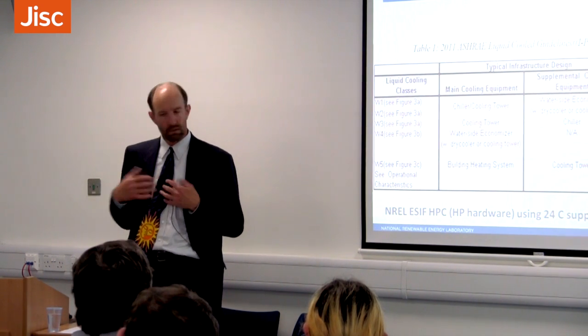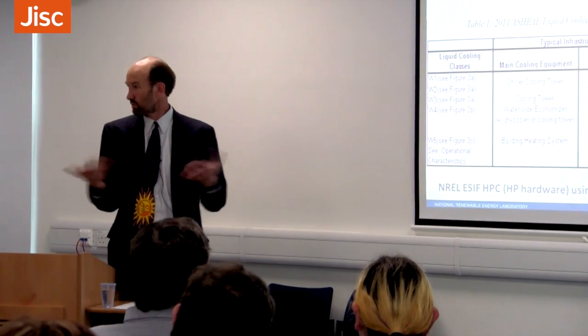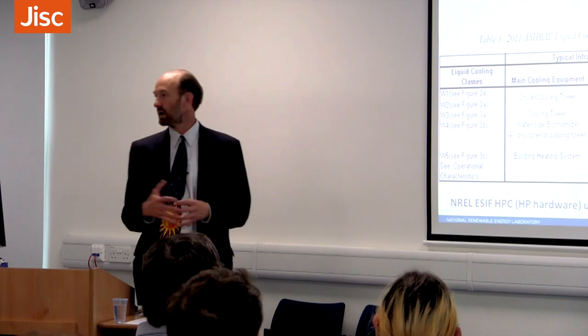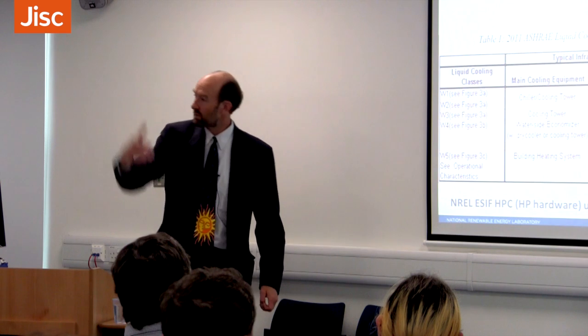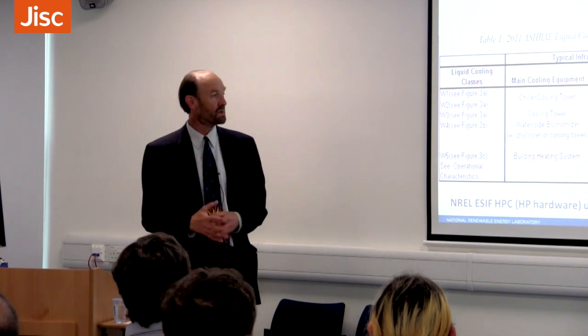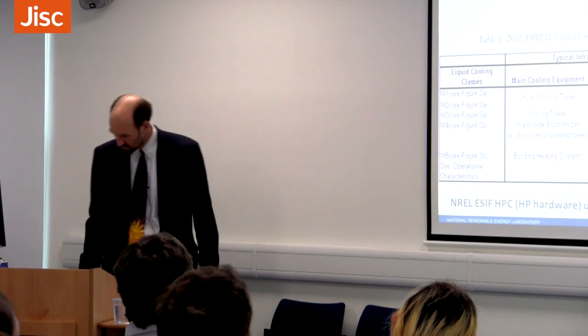A question: can you explain if you're using heat pumps? No — it turns out for laboratory buildings like this complex, you don't need real warm water to heat the air. You only need to heat it to room temperature. You need a slightly bigger, deeper coil because the temperature is a little lower. You could do it with heat pumps, but then you pay the energy for the heat pump — best if you can use it direct. Our RSF building uses radiant cooling and heating — the ceiling is a radiant slab, and you can use very low temperature water for all heating. 40°C is way above room temperature — you can do a lot with it.